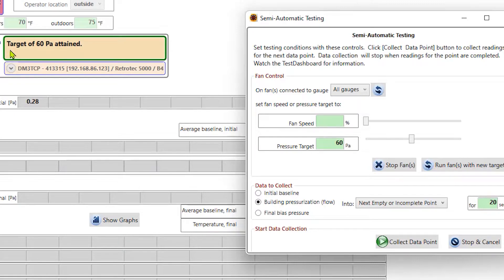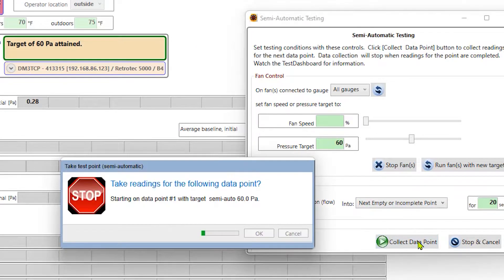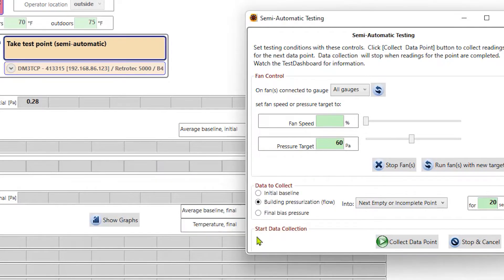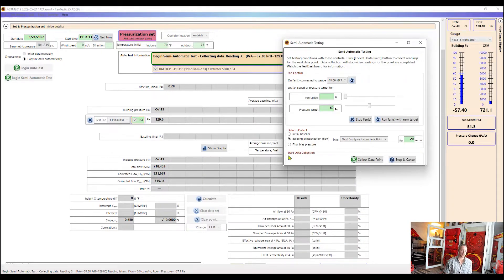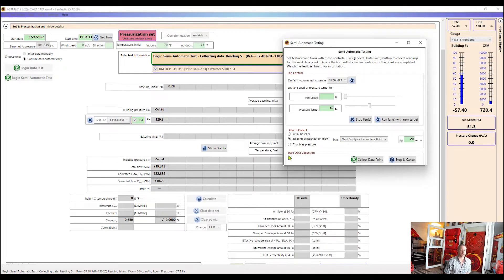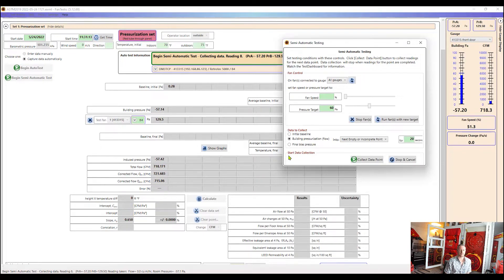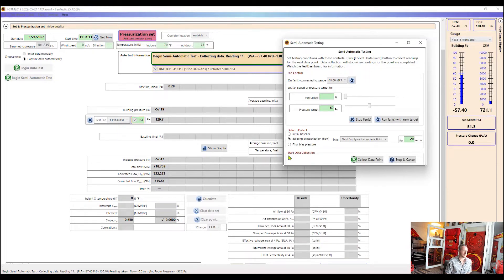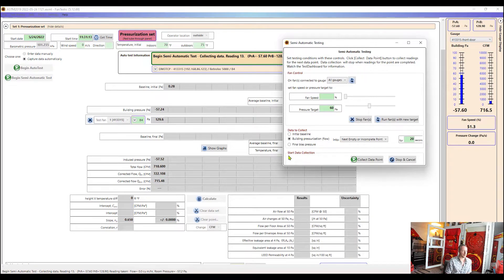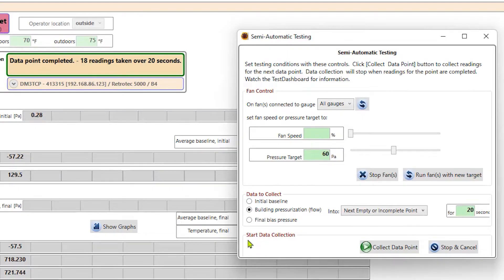So now we can see on this window here that our target of 60 Pascals has been attained. We want to look for that green border around there in that message to let us know that it's okay to go ahead and start collecting data now. So once we see that our target pressure has been attained, we can click collect data point. And then it will collect data at 60 Pascals for 20 seconds. Again, if we ever want to change that, we can go into our settings and let it know how long we want it to collect.